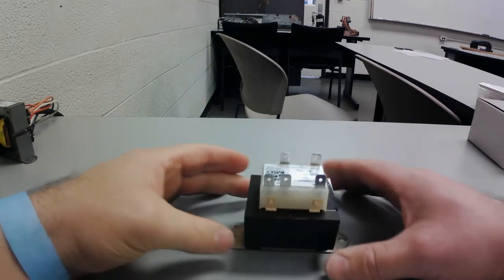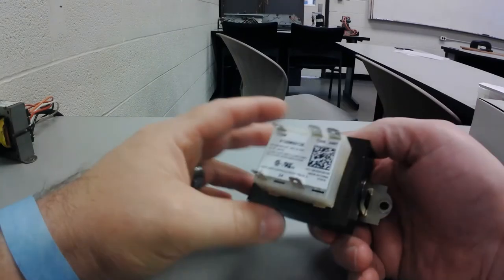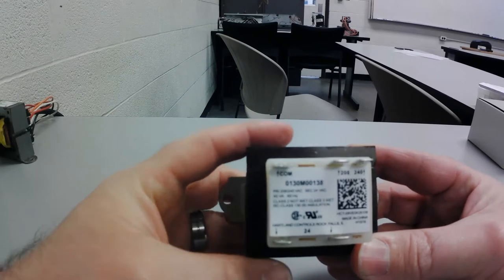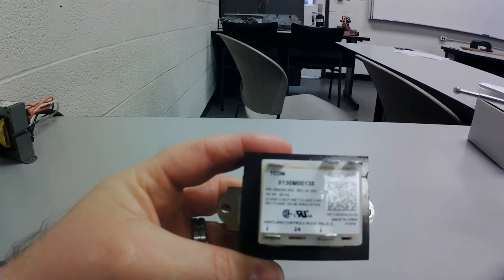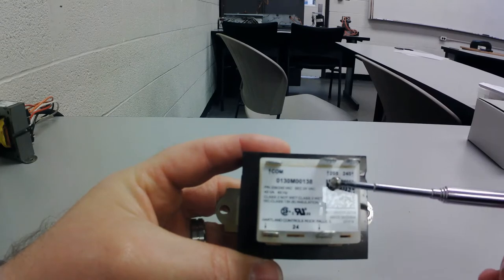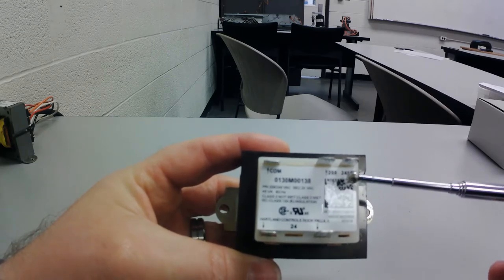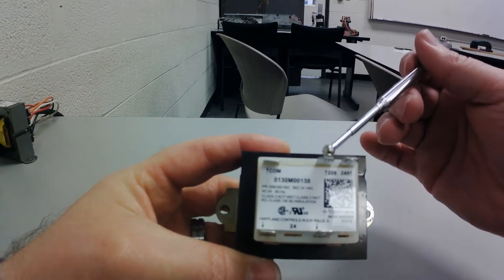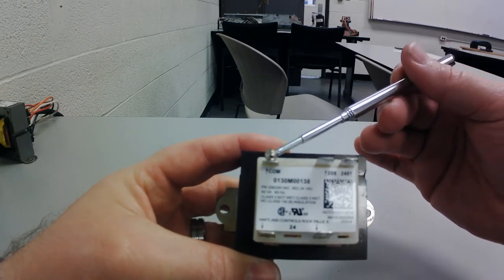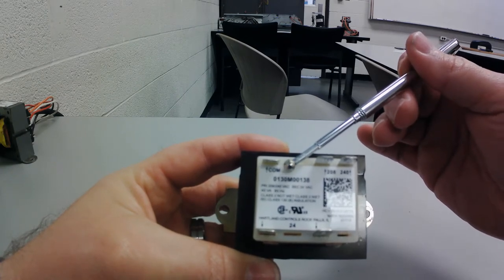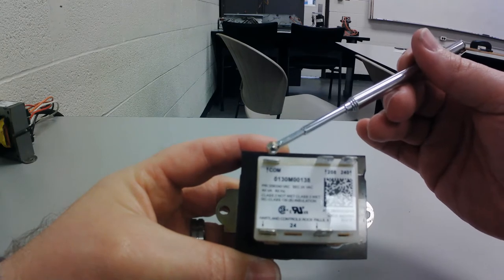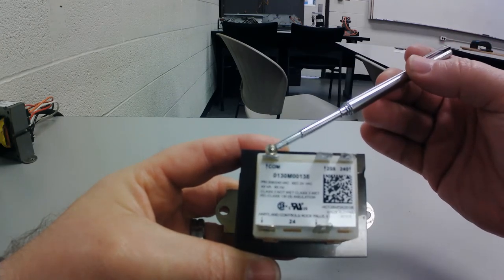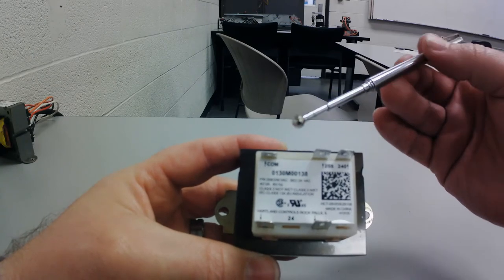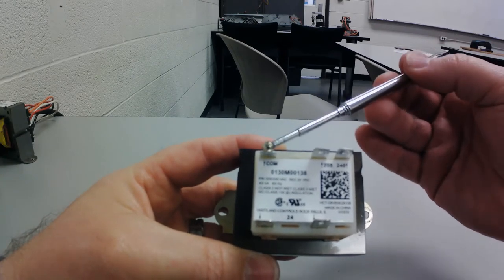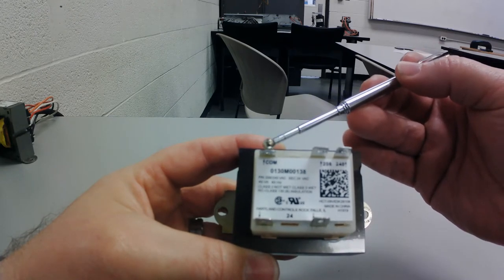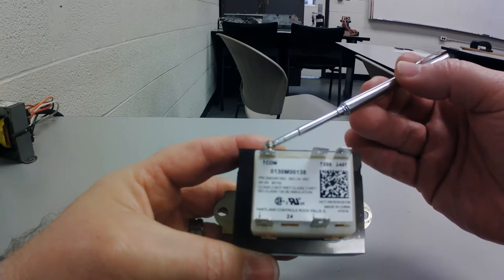Now this one is a multi-voltage input transformer, and you can see right here, this came out of a package unit that we have here. I have a 208 or a 240 volt input, and no matter which hot wire I put on here from a 208 power source or a 240, this is going to be my other side of power. They commonly list it as common, but this is not a common as in low voltage common. This is just a common output or return for, in some cases, a neutral or the L2. This is your other side of power.